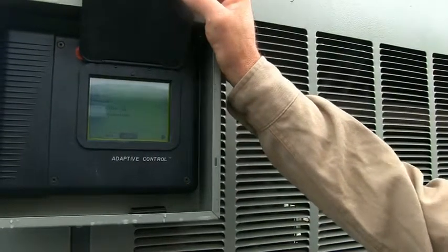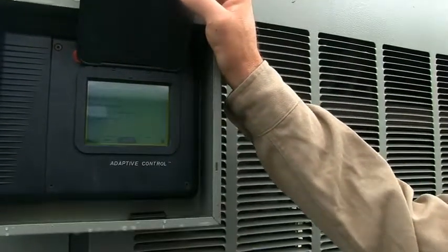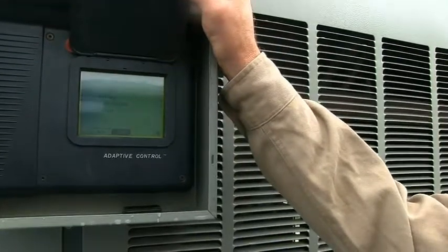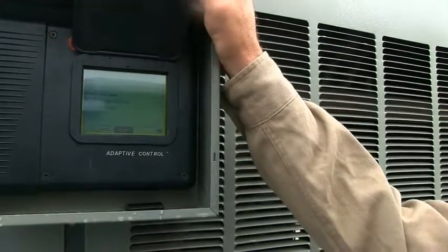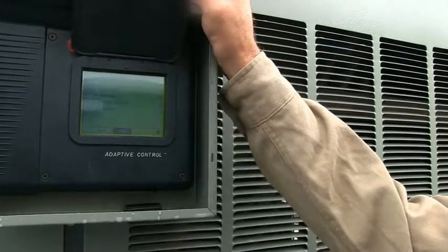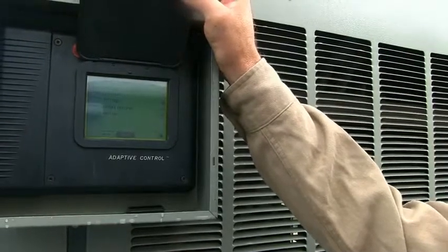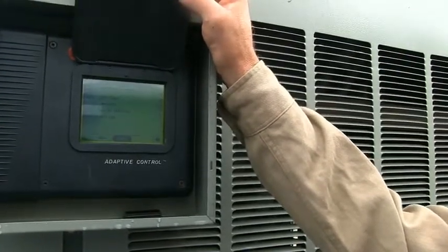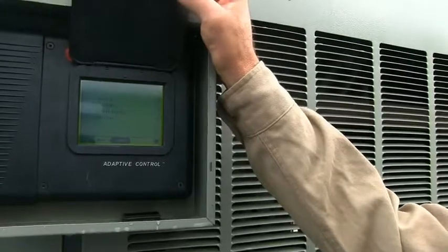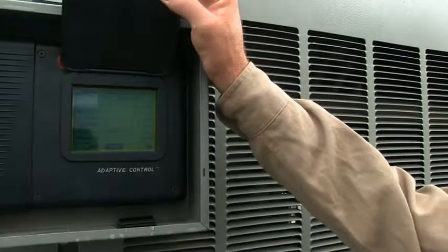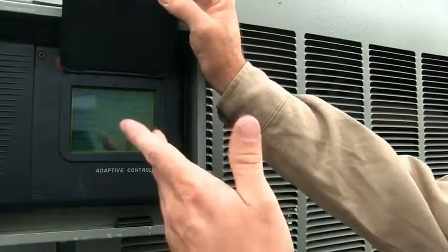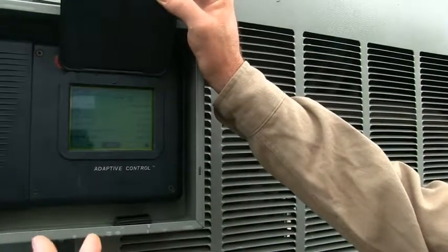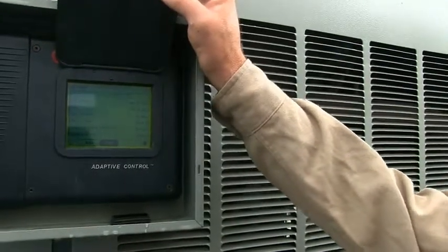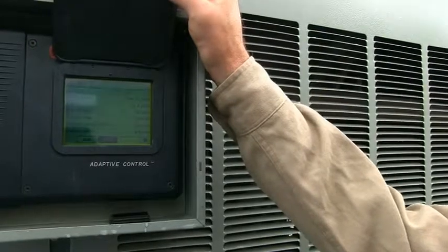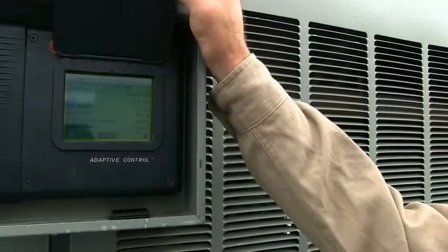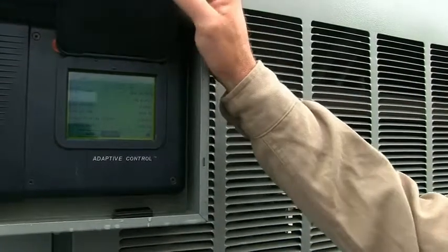The last category is settings. You hit the settings. That's basically how you configure the machine as far as the design delta, extended pump run times, freeze avoidance, display settings. You can set the clock. If you hit display settings, set the clock, date. You can also lock out individual circuits, individual pumps. Basically that's it.